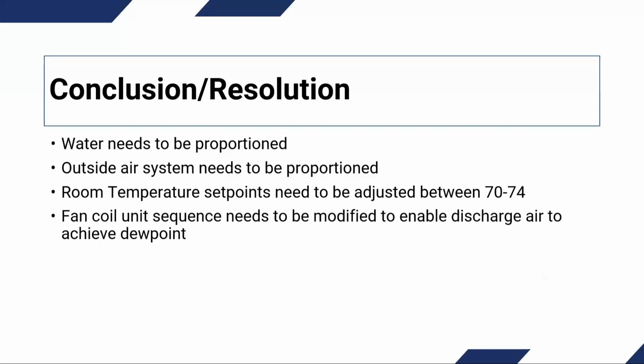One of the main things that we needed to do was we needed to change the sequence of operation on the fan coil units to make sure that the fan coil units could achieve dew point, because currently the way they were modulating to maintain space temperature, they were never reaching dew point.